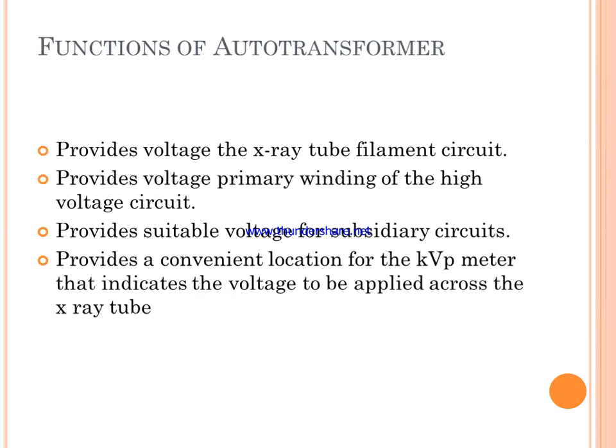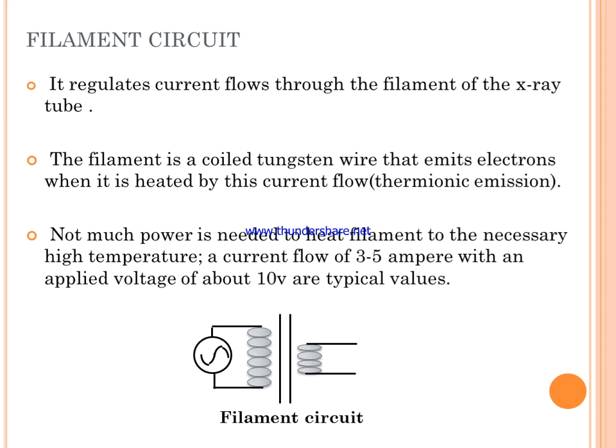The functions of the auto transformer include: providing voltage to the X-ray tube filament circuit, providing voltage to the primary winding of the high voltage circuit, providing suitable voltage for subsidiary circuits, and providing a convenient location for the kVp meter.